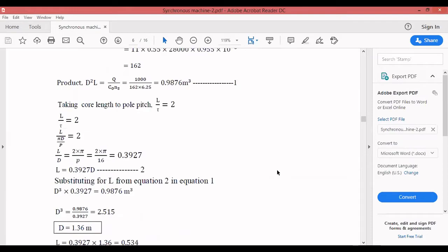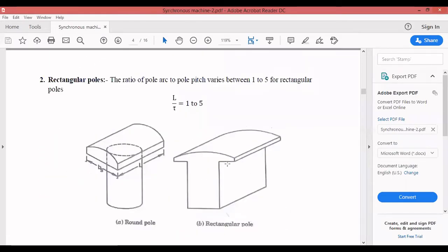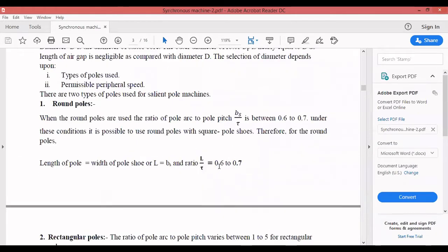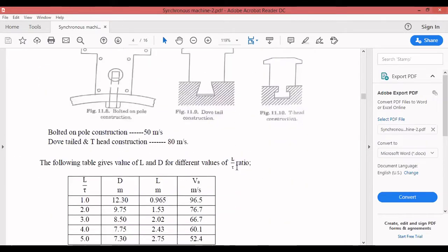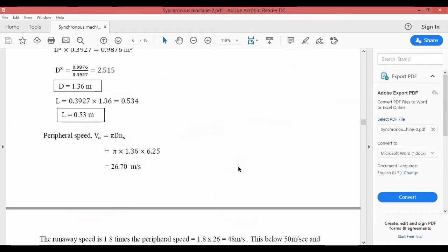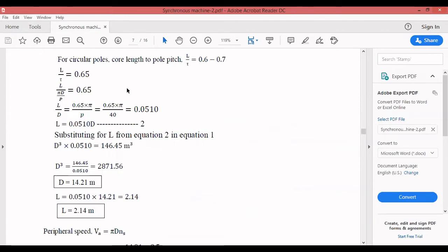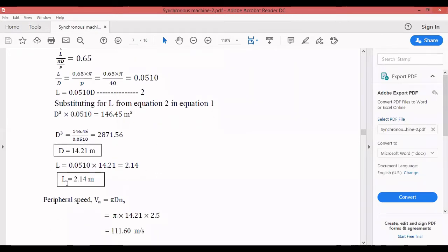For circular poles, L/τ is between 0.6 and 0.7; I take L/τ = 0.65, which gives L = 0.051D (Equation 2). Substituting into Equation 1: D ≈ 14.21 m and L ≈ 2.14 m. Note: in an induction motor D and L are fractions like 0.2–0.5 m, but in an alternator they are much larger.